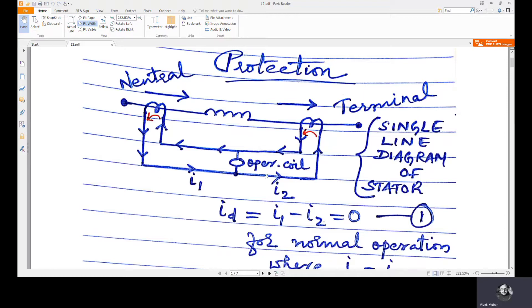This circuit is the secondary circuit of the CTs which are interconnected. If there is no fault in the generator, that means there is no fault in the stator winding, then the direction of current would be like this — it will follow the same direction. The CT1 primary current and the CT2 primary current will have the same direction.